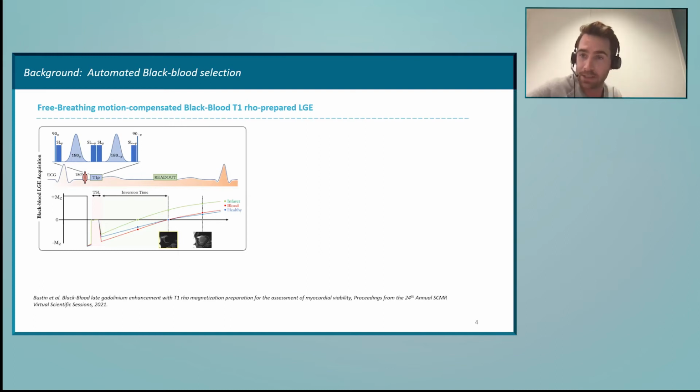Exactly. But you're right, Jérôme, for the conventional acquisition. That's why we sometimes have a shift in TI of plus or minus 20 milliseconds depending on the center, because of the apparent TI. But that's not the case here. The sequence is exactly the same.